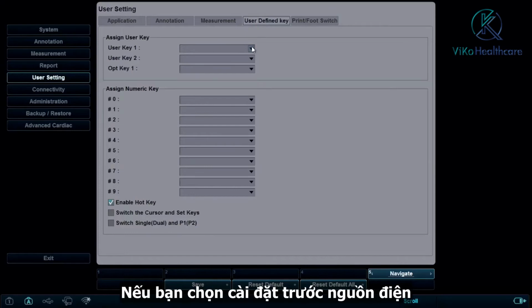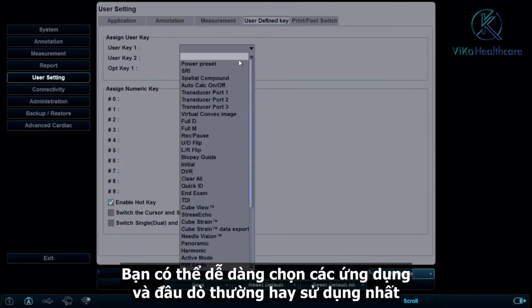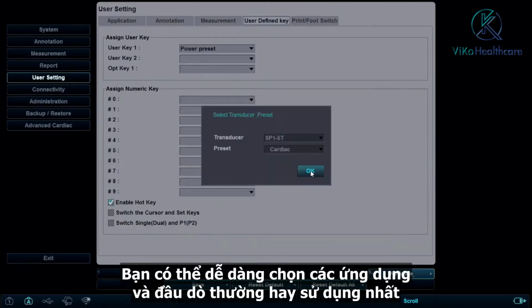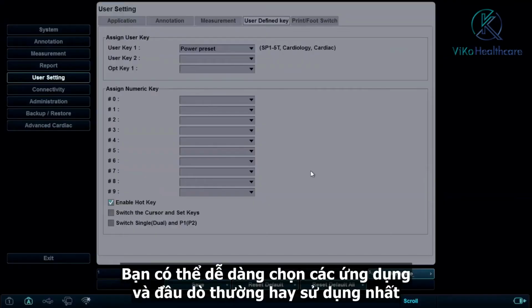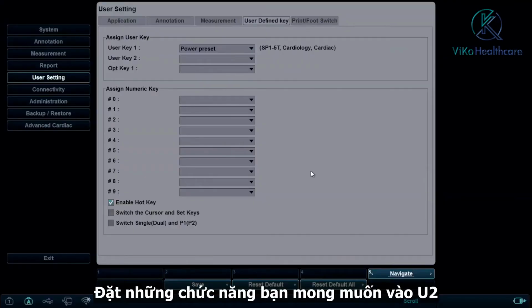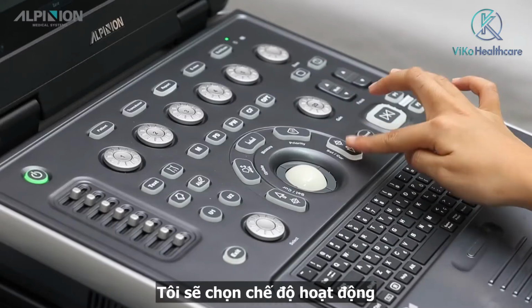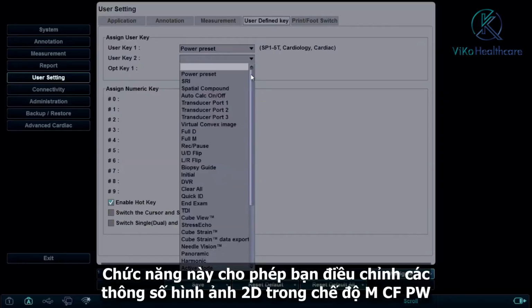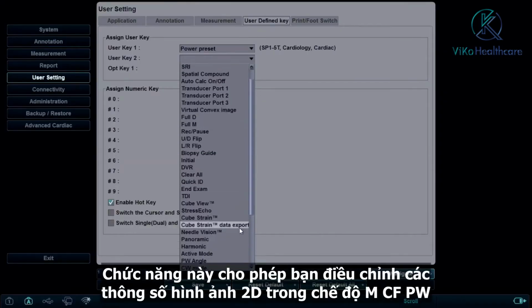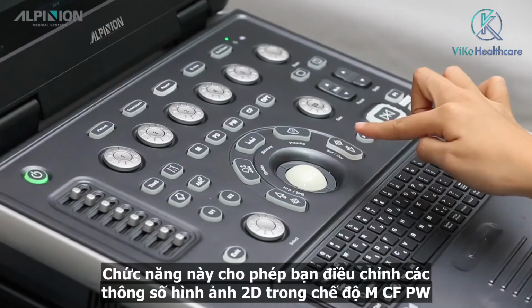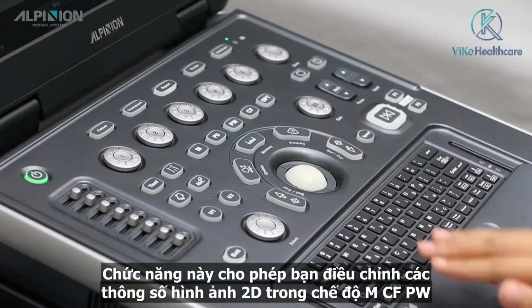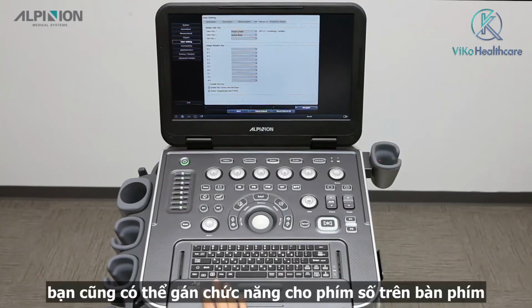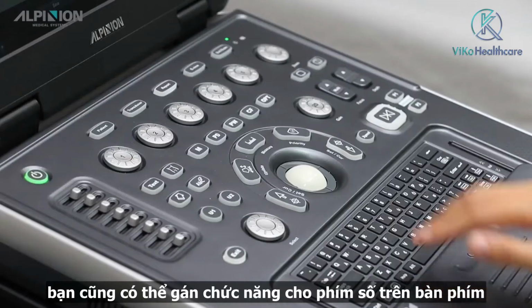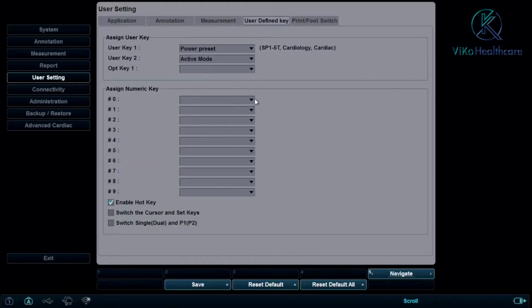If you choose Power Preset, you can easily set your most frequently used transducer and application. Set U2 as your desired function. I will select Active Mode. This function allows you to adjust 2D image parameters in M, CF, PW modes. Also, you can assign function to numeric key on keyboard.